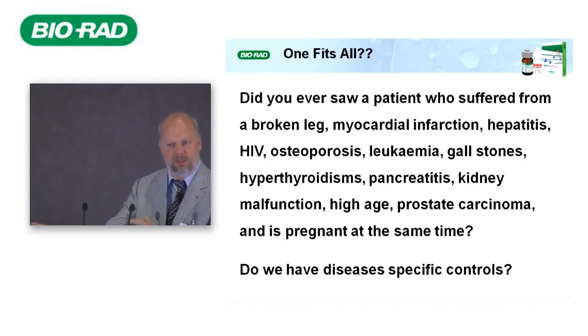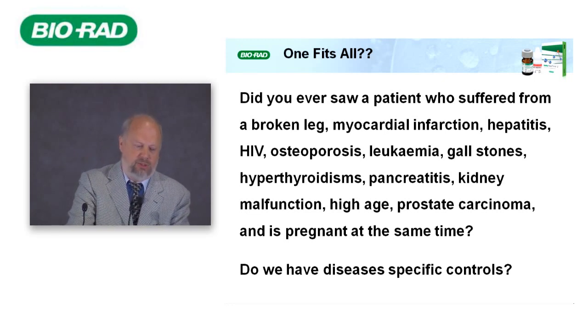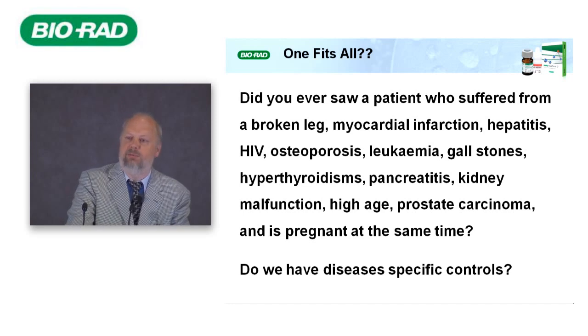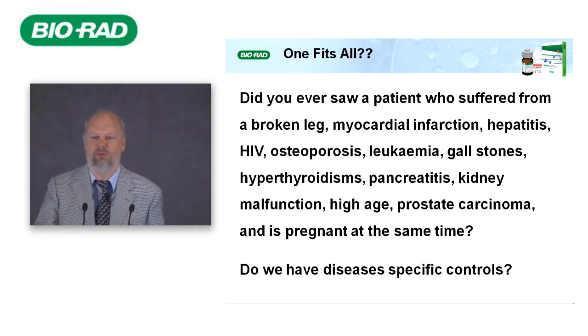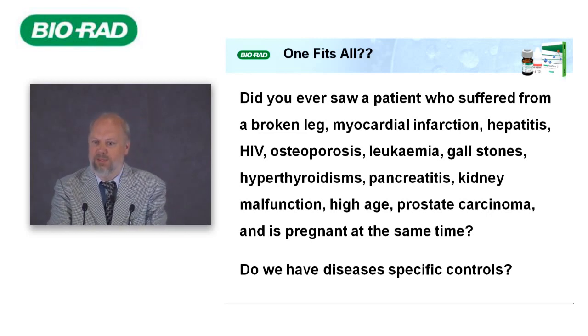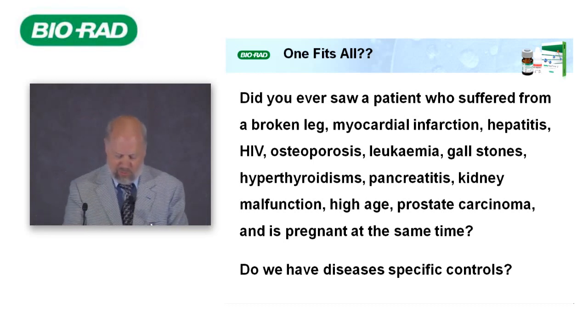My question — and this is the wish of the laboratory — is one fits all. Did you ever see a patient suffering from a broken leg, myocardial infarction, hepatitis, HIV, osteoporosis, leukemia, gallstones, hyperthyroidism, pancreatitis, kidney malfunction, high age, prostate carcinoma, and pregnant at the same time? That's essentially the quality control we use — a control with all analytes in extremely high concentration. Maybe it's time to ask for disease-specific controls, because we take care of individual patients.